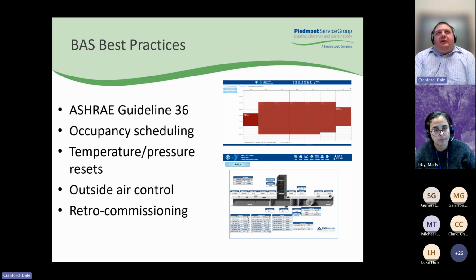A big topic of conversation in recent years on the building automation side is outside air control. In a lot of cases, try to use outside air economizer for free cooling whenever you can, when outside air conditions are favorable. And then you can look at doing demand control ventilation using CO2 sensors to reduce the amount of outside air down to the ASHRAE 62.1 minimum area flow rate. You do need to make sure you at least maintain that, but you can reduce the people flow rate when the CO2 levels are good. But you do have to be careful. If you open up the outside air too much with CO2, your system may not be able to handle the amount of load that the additional outside air puts on it, depending on how it was designed.